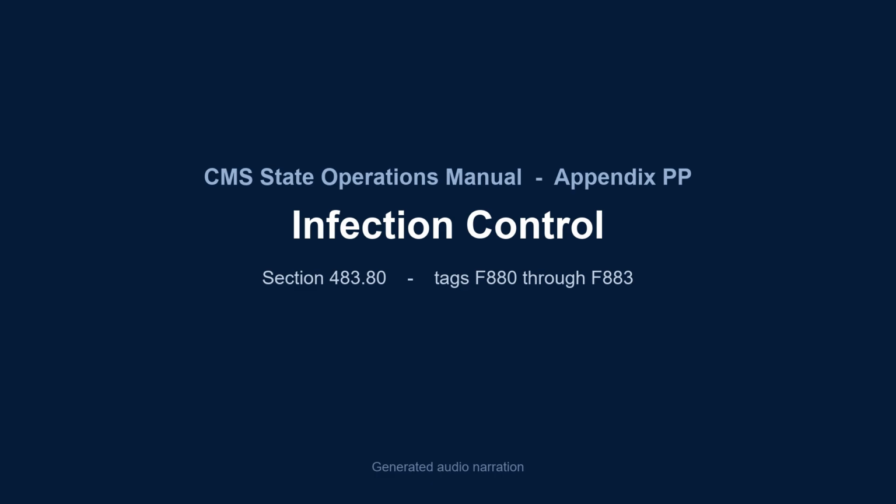Semi-critical items, e.g., dental, podiatry equipment, electric razors, contact mucous membranes or non-intact skin. Such items require meticulous cleaning, followed by high-level disinfection treatment using an FDA-approved high-level chemical disinfectant, or they may be sterilized. High-level disinfection is traditionally defined as complete elimination of all microorganisms in or on an instrument, except for small numbers of bacterial spores. Refer to the specific disinfectant label claim to determine effectiveness.